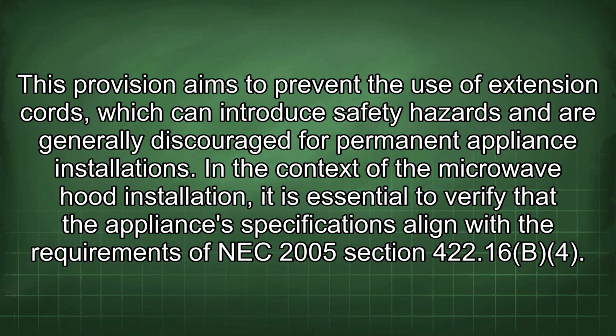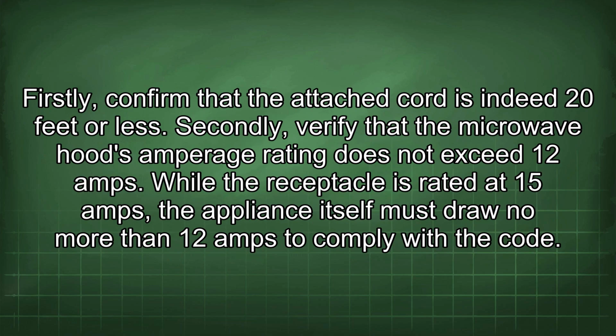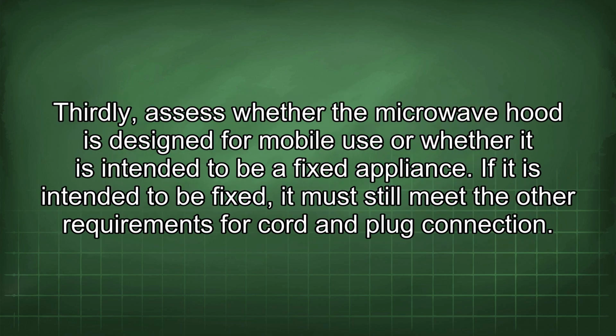align with the requirements of NEC 2005 Section 422.16b4. Firstly, confirm that the attached cord is indeed 20 feet or less. Secondly, verify that the microwave hood's amperage rating does not exceed 12 amps. While the receptacle is rated at 15 amps, the appliance itself must draw no more than 12 amps to comply with the code.